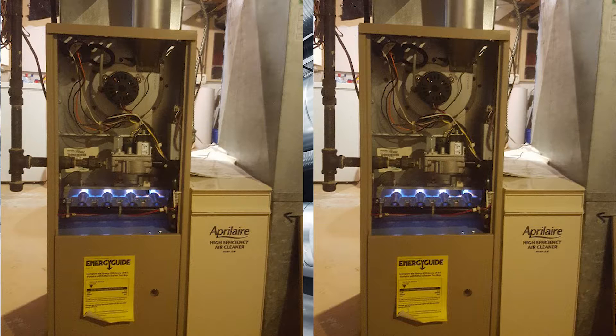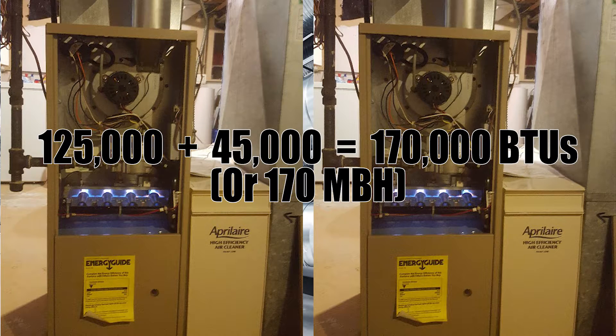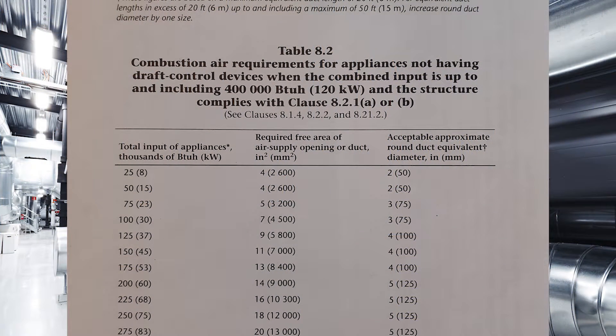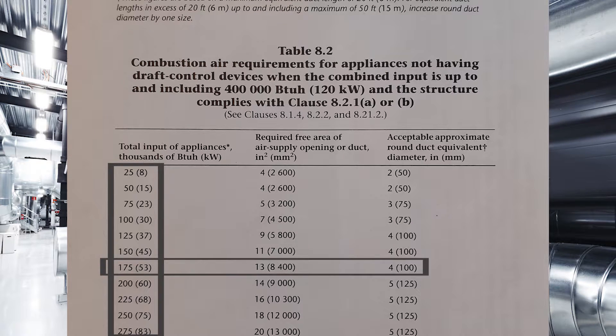For my next example I have two fan-assisted furnaces: the first is 125,000 BTUs and the second is 45,000 BTUs. Adding those together gives a total BTU load of 170,000 BTUs. Both appliances are fan-assisted, meaning they are not equipped with draft control devices, so I need to go to table 8-2. Once again I go down the far left column looking for 170,000 BTUs — it's not there — so I go to 175,000, go across to the far right, and I need a 4-inch air supply.